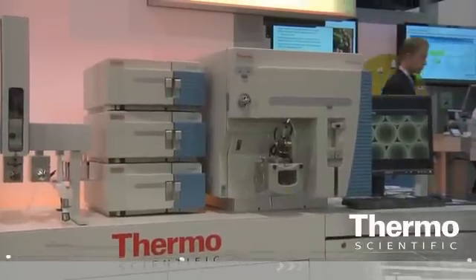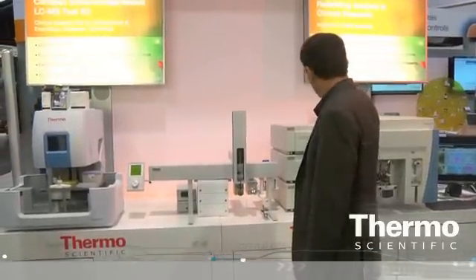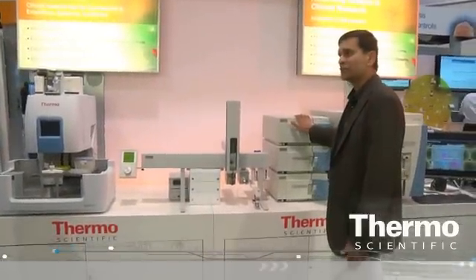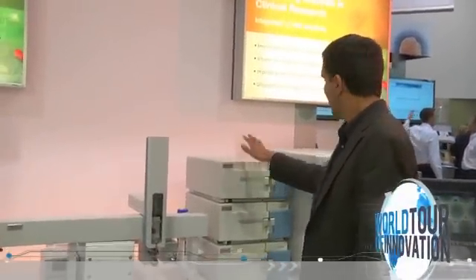What happens next is the Transcend TurboFlow sample preparation, or sample cleanup. This is one of the critical steps in the analysis using MS-MS, or triple quadrupole mass spectrometry. It cleans up the sample so well that there are no interferences detected during MRM-based analysis on a triple quadrupole system. This is TurboFlow online sample preparation to remove proteins, peptides, lipids, and salts. That's the penultimate step in the analysis.